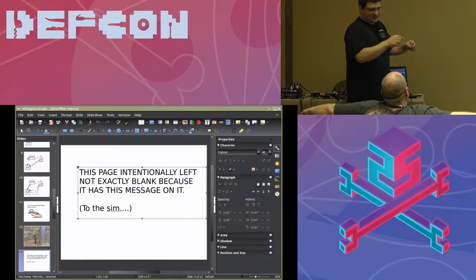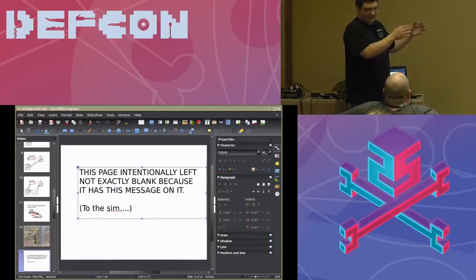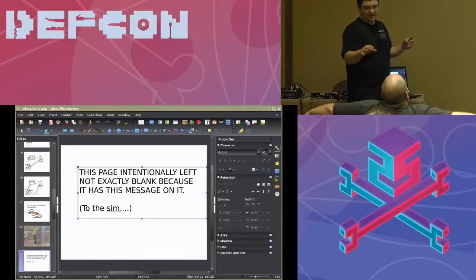Live, neutral, and ground: those three wires go back to your panel. At your main panel—if you have a sub-panel this isn't necessarily true—but at your main panel, the neutral and ground just connect together. So it's like a second path for neutral, but one that doesn't carry current.